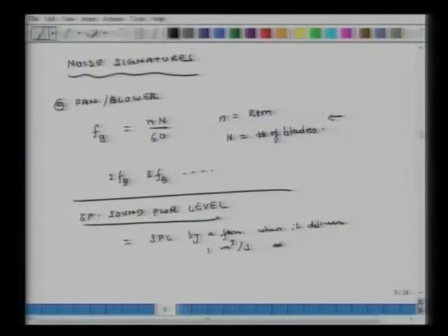at 1 kilopascal, so it's 1 kilopascal above atmospheric air pressure. So if I have 2 totally different fans, one delivering 20 cubic meters at so many pascals and the other delivering some other number of cubic meters at some other pressure level, if I bring it down to this specific sound power level, I can figure out how much noise is generated. I can compare the noise characteristics of 2 fans.